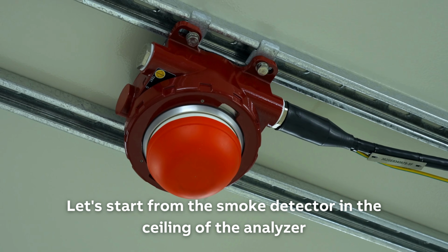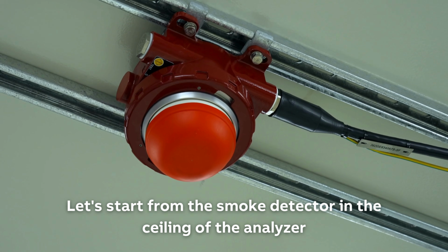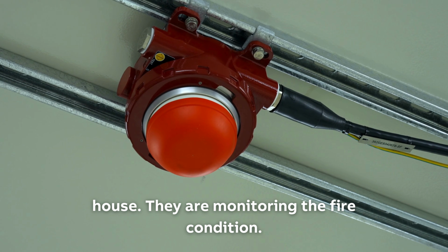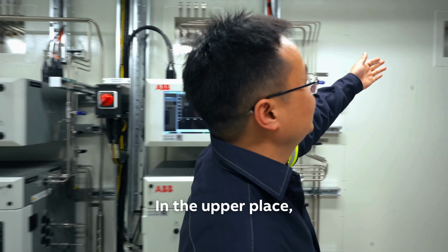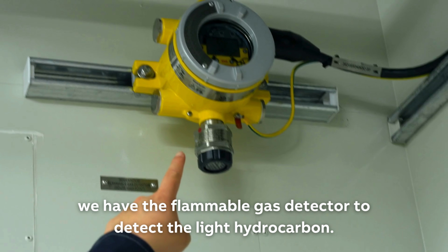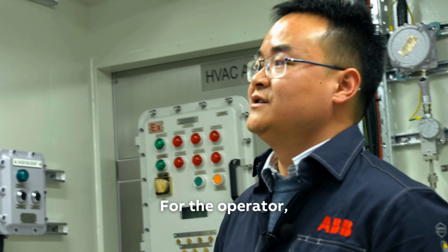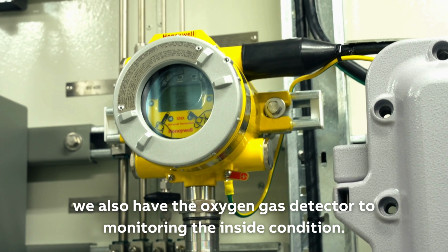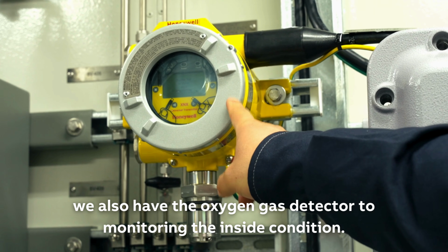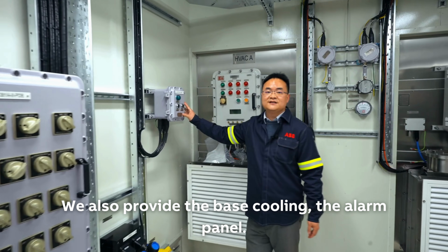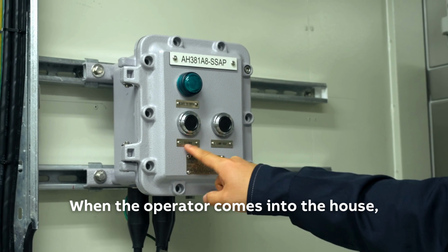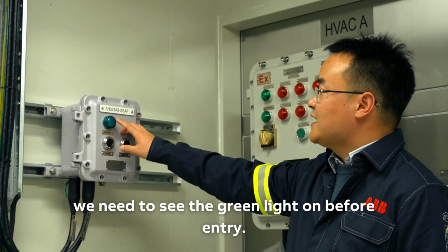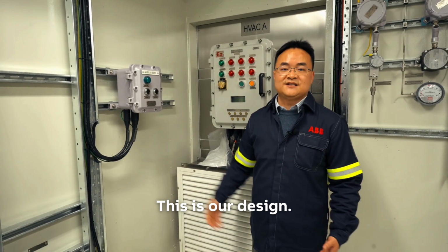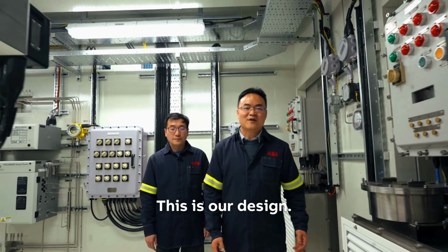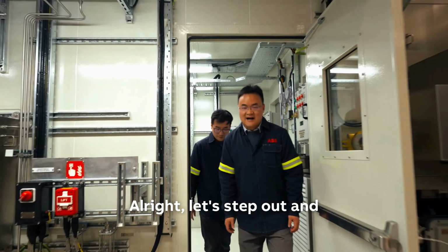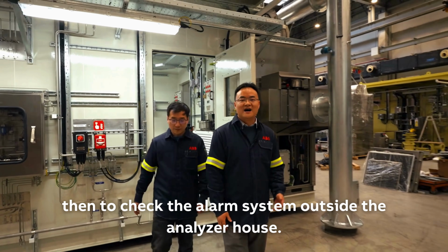Let's start from the smoke detector in the ceiling of the analyzer house. They are monitoring the fire condition. In the upper place, we have the flammable gas detector to detect light hydrocarbon. For the operator, we also have the oxygen gas detector to monitor the inside condition. We also provide a basic alarm panel. When the operator comes into the house, we need to see the green light on before entry. That is our basic design. All right, let's step out, and then check the alarm system outside the analyzer house.